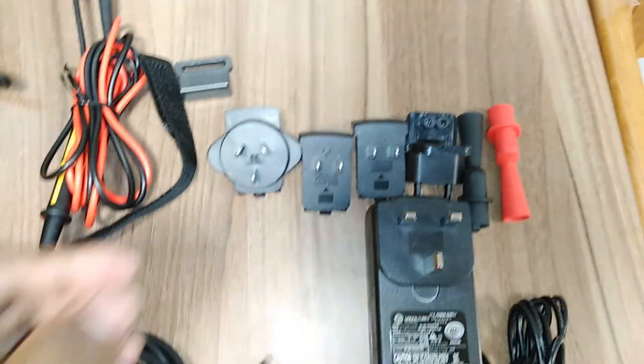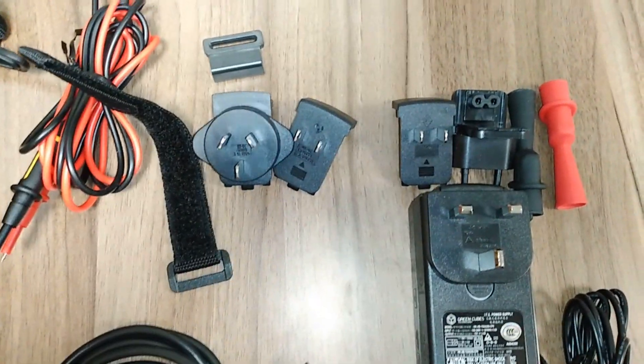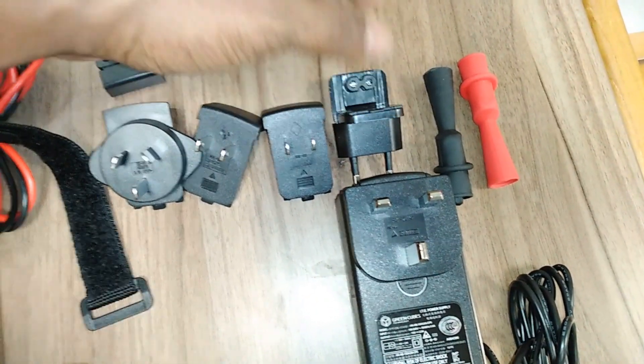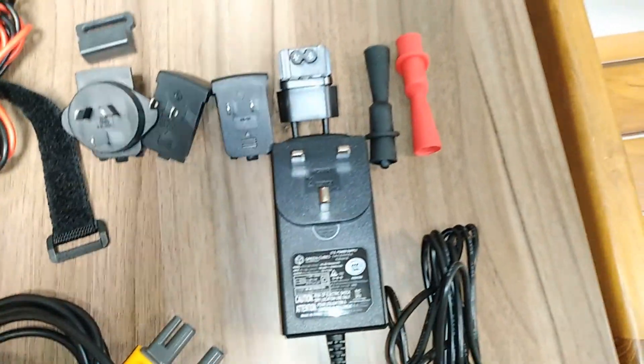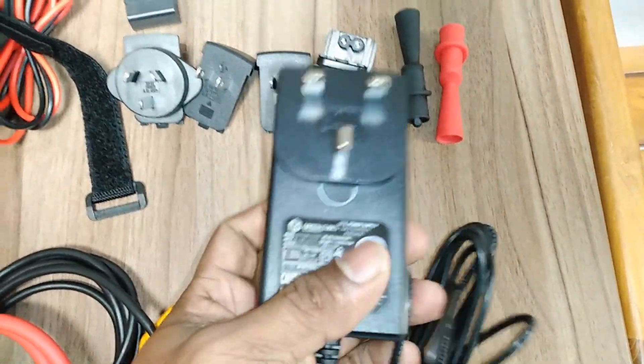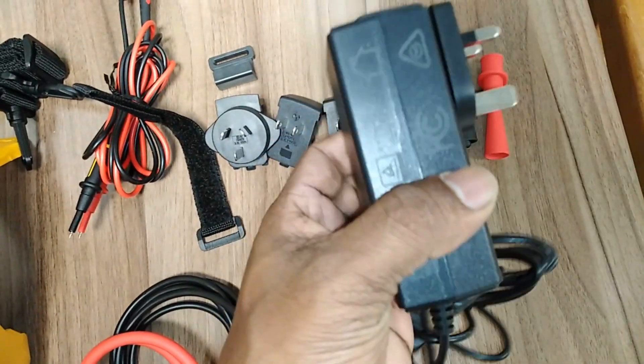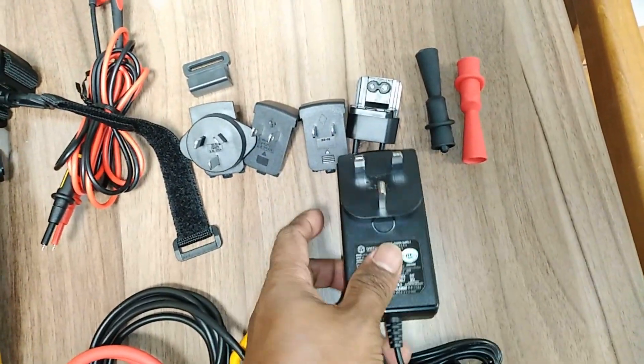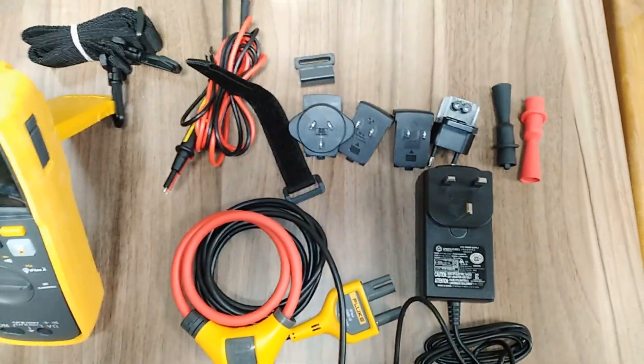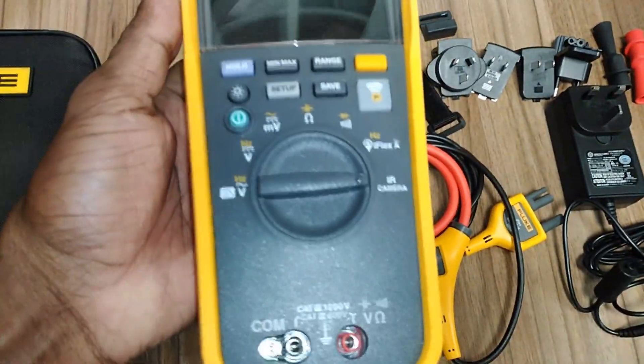Carefully read all instructions and safety information before you use the product. Examine the case before use — look for cracks or missing plastic, and carefully look at the insulation around the terminals. Do not use the flexible current probe if it has damaged insulation, exposed metal, or if the wear indicator is visible. You also need to physically check and examine the test leads for damaged insulation, exposed metal, or worn conductors.